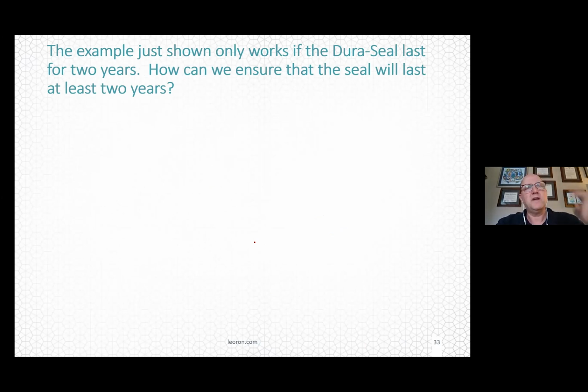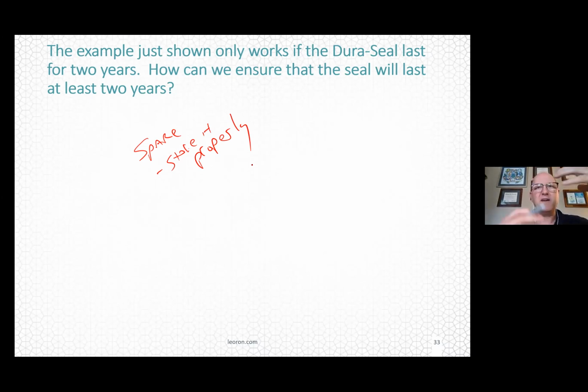The things I've got to do to ensure it lasts 2 years: store the spare seal in the storeroom properly. If it's affected by heat, humidity, or sunlight—say it has rubber and UV exposure—I've got to guard against that. If it's a mechanical seal, I've got to guard against vibration from the shelves; I don't want to put it on a metal shelf. I've got to store it in the box and wrapping it comes with, protect it in the storeroom, so when I put it in it has a chance of lasting 2 years.